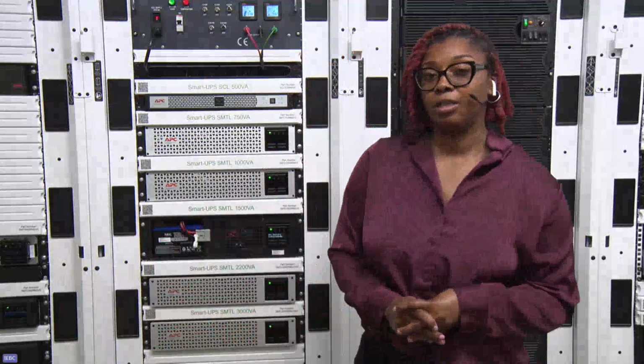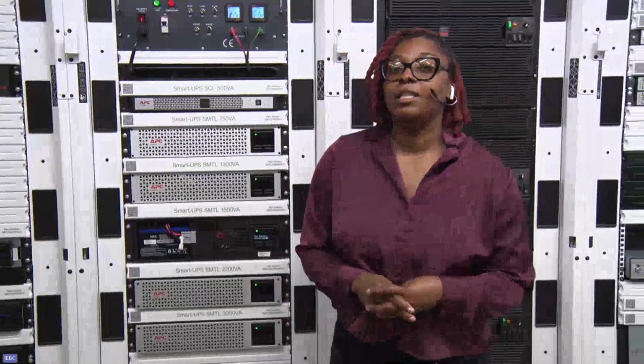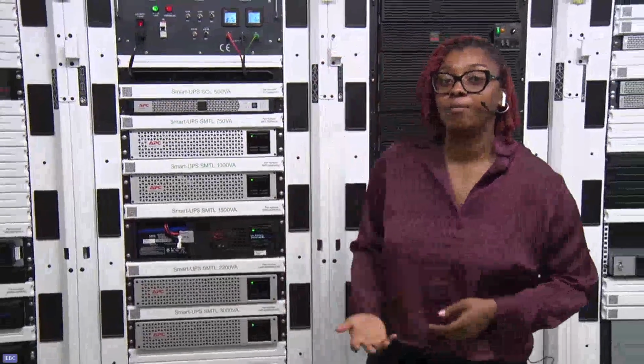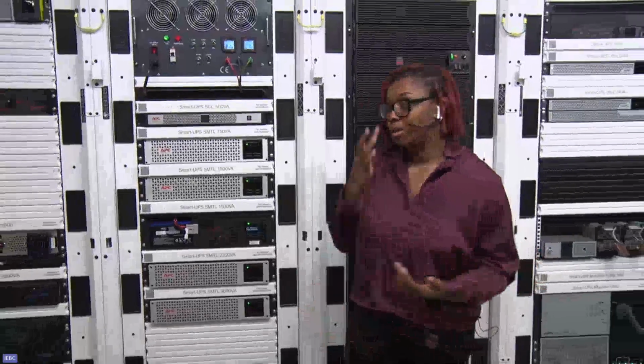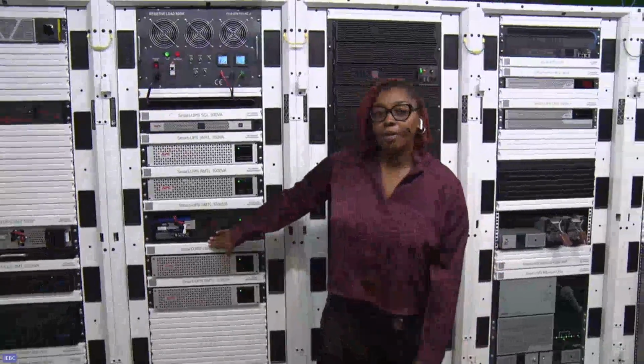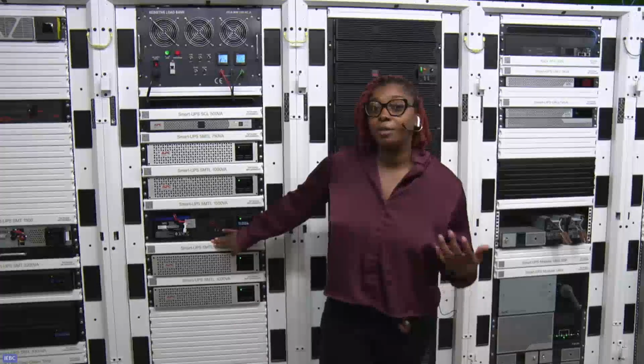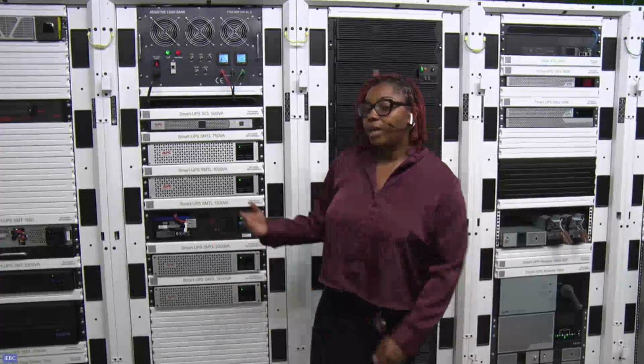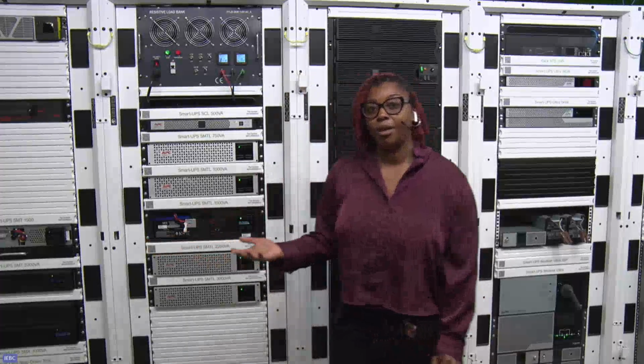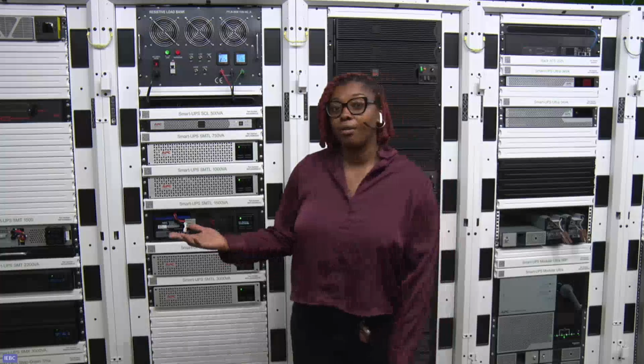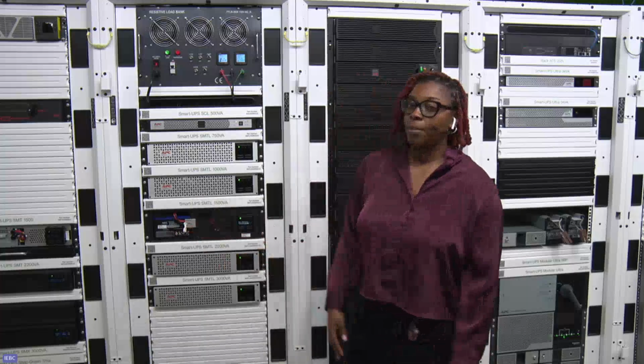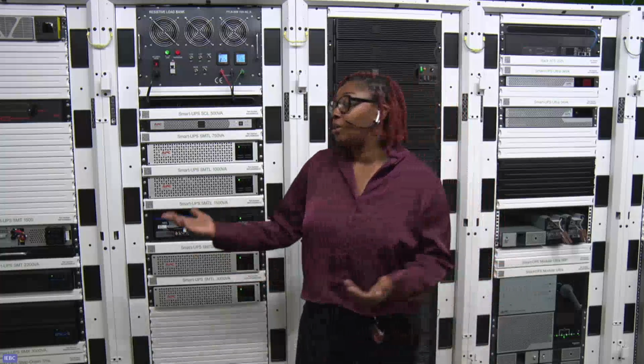When we compare lithium ion batteries and lead acid batteries, you want to look at the lifespan. VRLA batteries last 3 to 5 years, where lithium ion batteries last 7 to 10 years. What that means is this lithium ion battery can last the entire lifespan of the UPS system itself. With your lead acid batteries, you're probably going to have to do maybe 2 to 3 battery changes, refreshes throughout the lifespan of the UPS system.